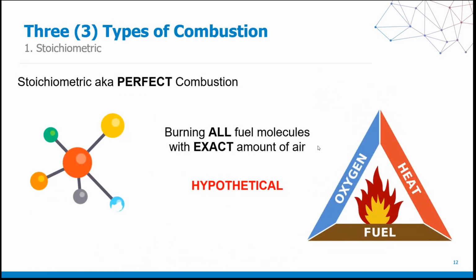When we talk about combustion, we have three different types. The first is stoichiometric. Stoichiometric is otherwise known as perfect combustion. And it's a hypothetical, it's a lab condition, and it doesn't exist. And it does not exist for these two specific reasons. The first and most primary is that stoichiometric assumes that we have 100% oxygen for our combustion process. And for those of you that currently use a combustion analyzer, and even if you don't, you know that the oxygen in the air that we breathe is 20.9%.